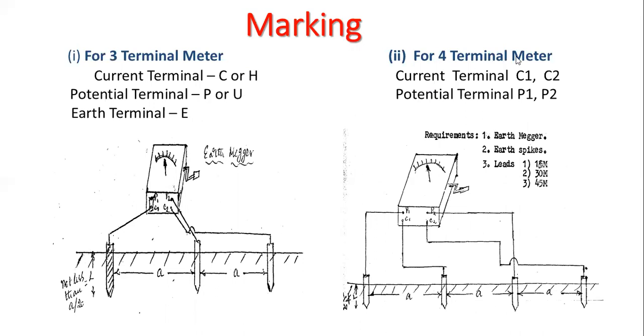Then for the 4-terminal meter, the current terminals are C1, C2 and the potential terminals are P1, P2. These 4 terminals are connected to the earth electrodes at equal distances. So we can say 15 meters between the first 2 electrodes, then 30 meters between the first and third electrode, then 45 meters between the first and last electrode. That means all these electrodes are placed at an equal distance.